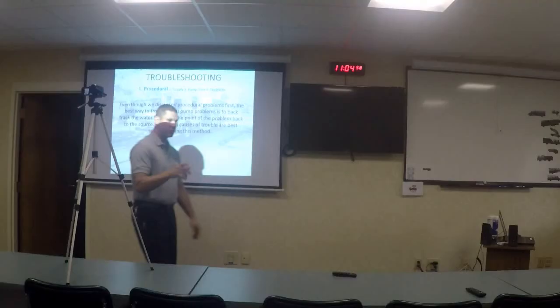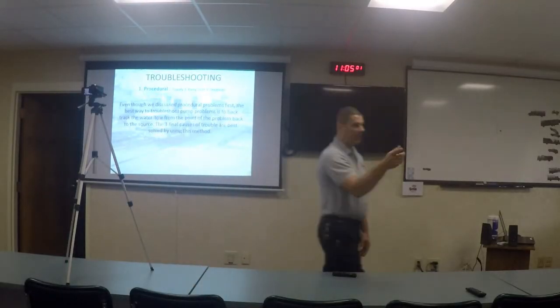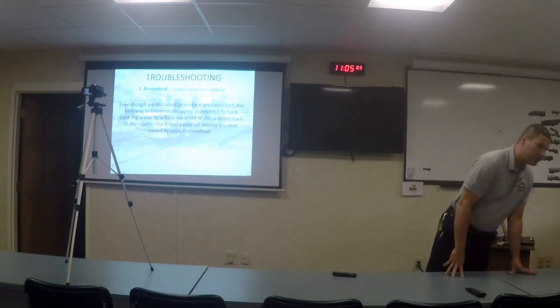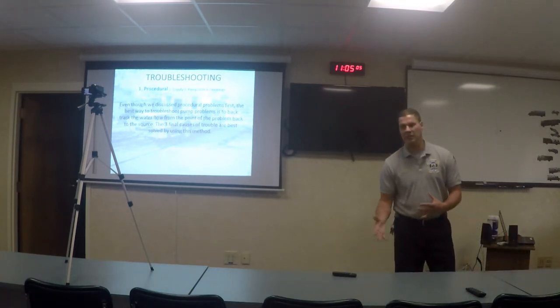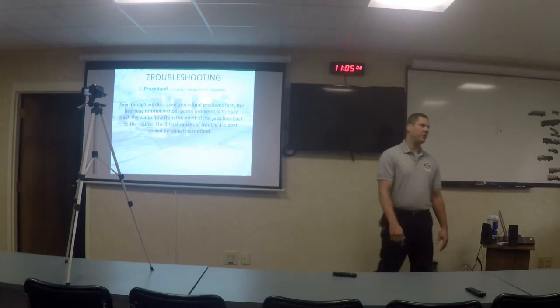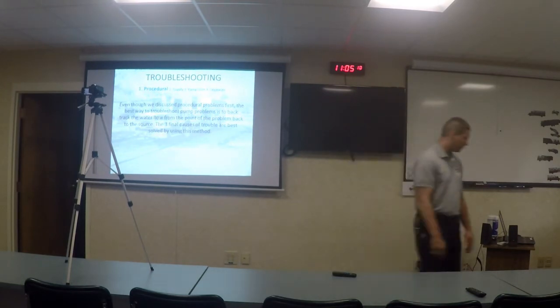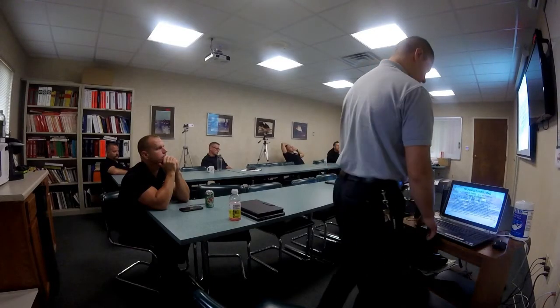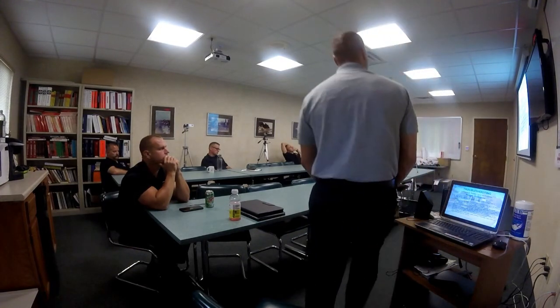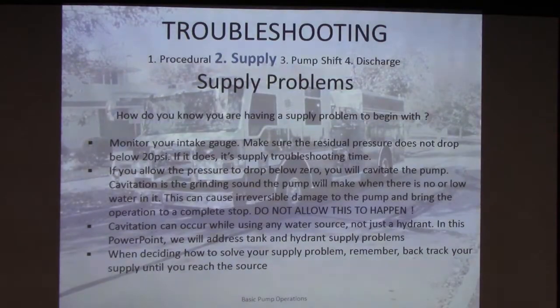But the other thing you do besides doing that is you can trace the water back to the start. And by doing that, you're gonna look real quick at the hydrant just to make sure that there's no kinks in it, the hydrant hasn't failed, supply line hasn't failed. Those are your quick checks. All right, so you monitor your intake gauge. The residual pressure should not drop below 20. What will happen if you let it drop below 20? Damage the pump and the water lines, right? Okay.